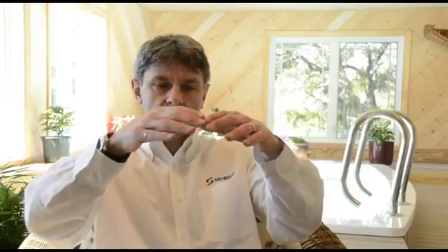One of the things you can also do from an air quality standpoint is, if you've got a hot tub, they spew a lot of chemicals. They've got the bubblers going on, the water's very warm, so you've got a lot of chemicals getting off-gassed into the space. If you've got an exhaust air requirement anyway, you might as well try to put an exhaust air intake right over the hot tub, and then you can sort of source capture those chemicals while they're off-gassing and get them out of the room before they have a chance to diffuse and kind of wreck the air quality. So some spot exhaust air on the warm bodies is definitely a way to go from an air quality standpoint.